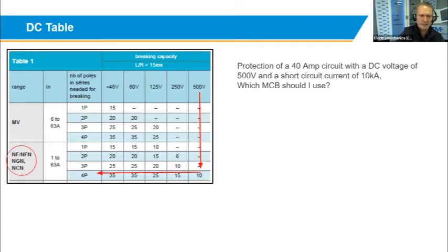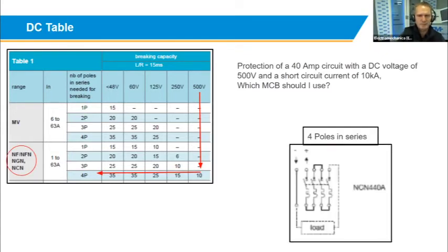So reaching your 10 kA, you can go to the left, and it will then mention to you that you must use a 4-pole product, and you can use any of the ranges on the left, NFN, NGN, NCN, again, depending on the tripping curve that you would like, B, C or D curve. And then 4-pole is, sorry about the snapshot I took out of the Hager catalog. It's not the best picture, but you can see there, that's the way you will then wire up a NCN 4-pole product to be used as 40 amp at 500 volts DC.